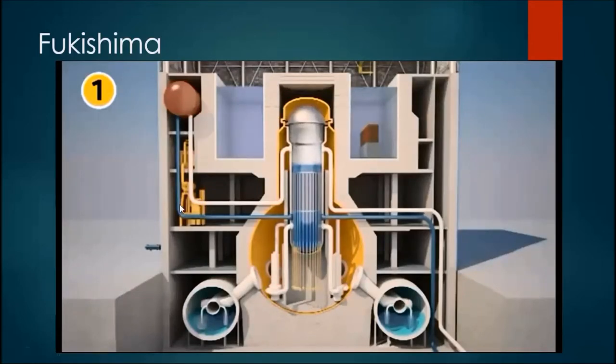So everything was working okay, and it was working perfectly, but they shut down this exchanger here because that was just normal. Shut it down, put it back on, shut it down, put it back on. So when the tidal wave came through, it wouldn't come back on. So now you have nothing cooling down this super hot reactor.